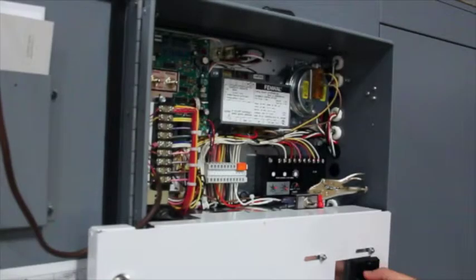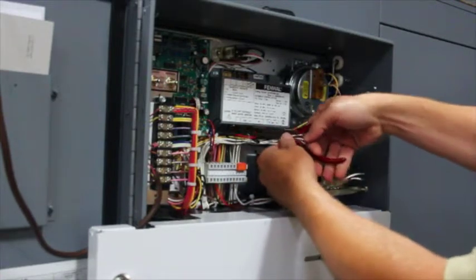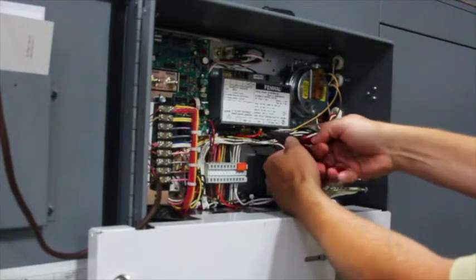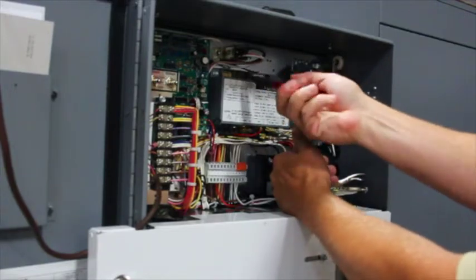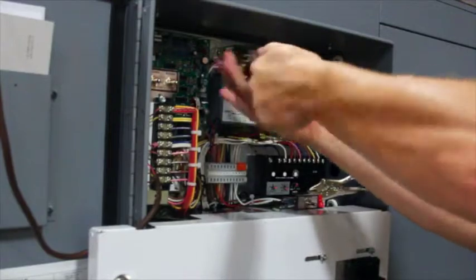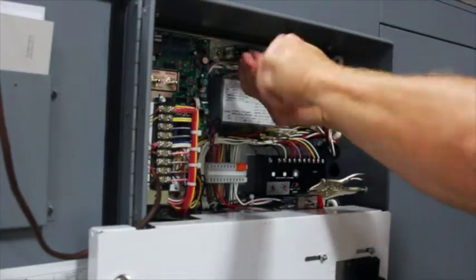To change the flame safeguard relay, first turn the disconnect switch to the off position and remove all existing wires on the original Fenwal flame safeguard relay board. Once the wires are removed, remove the two 1/4 inch screws which mount the flame safeguard relay to the sub-panel.